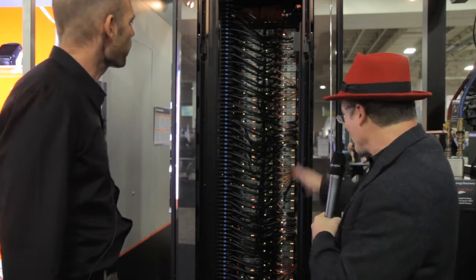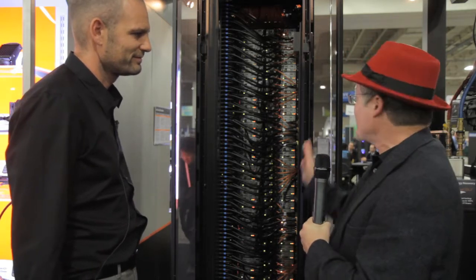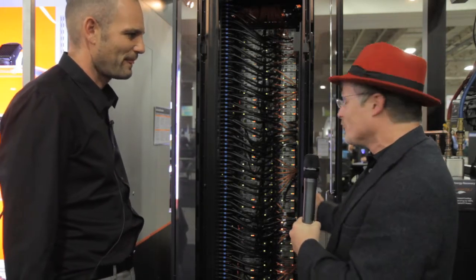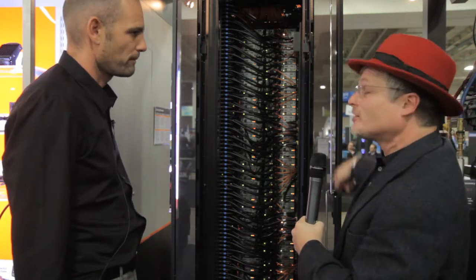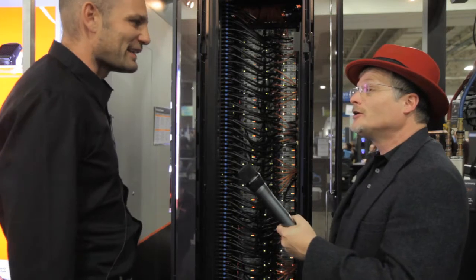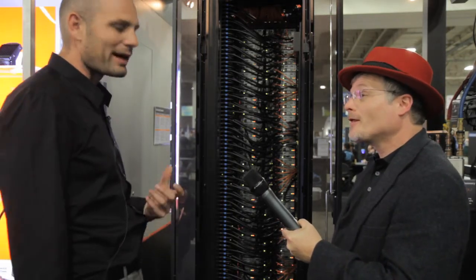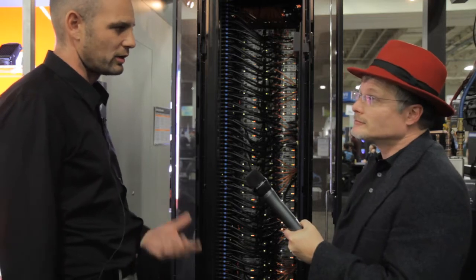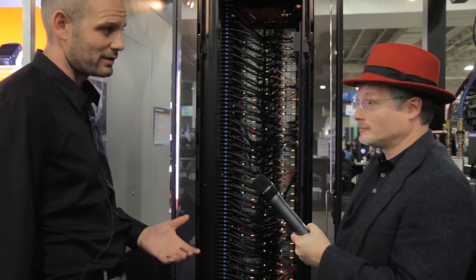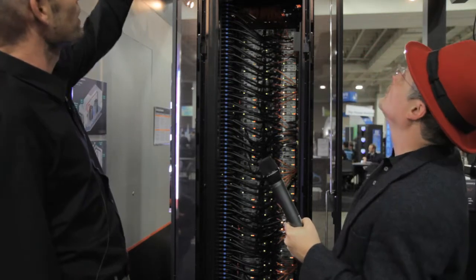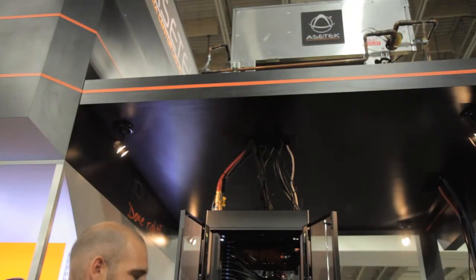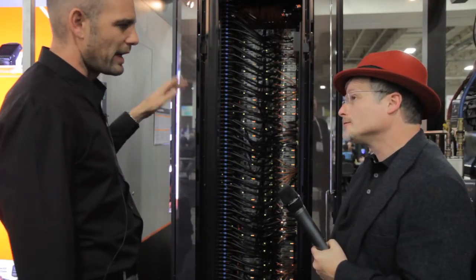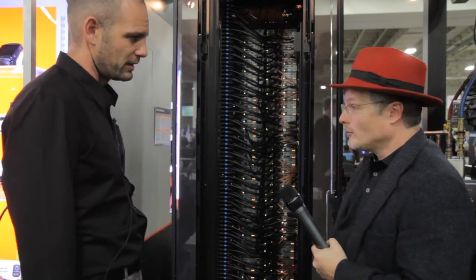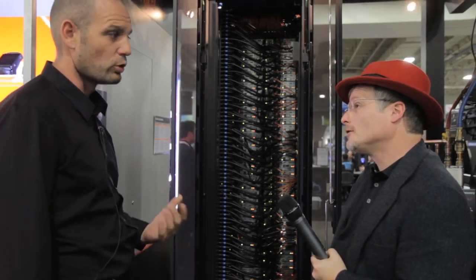So we've got this full rack, 37 kilowatts, probably the capacity of most racks. Are you removing the heat through a closed circuit water system? No, it's actually a hot water system. The reason I emphasize that is if it was cold or chilled water, you'd need to spend power chilling it. What we're doing is using something called a dry cooler, essentially a passive radiator like in front of your car with a slow running fan. We run liquid through each server, through our system, and up onto the roof of the building, using free ambient air to cool the data center.